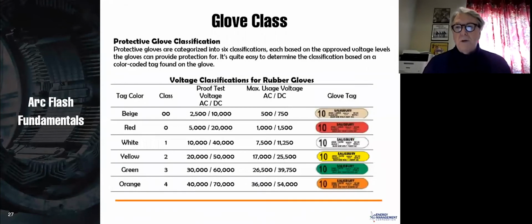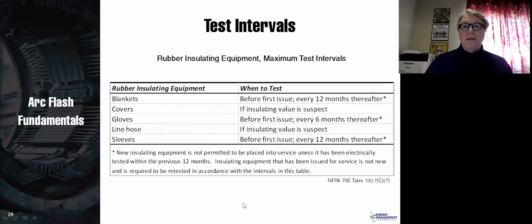Glove classifications are here. It is not required that you put glove classification on your arc flash label, but we do, and most people that I know of that do arc flash studies do, and that shows you your glove classifications. Test intervals. This, of course, is not fun, but gloves should be tested before you use them the first time and every 6 months thereafter.